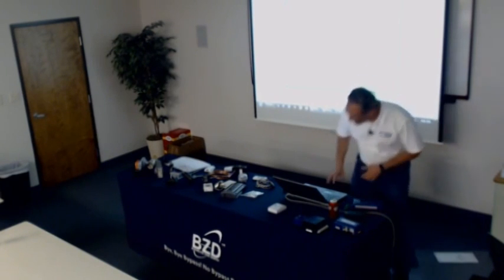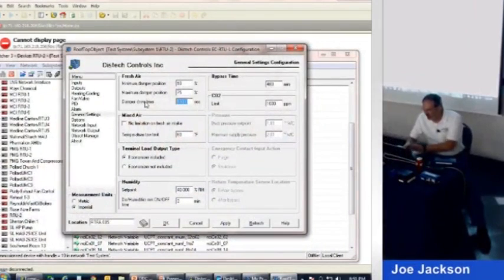So it keeps track of how long it told it to drive open, how long it told it to drive closed, and from that information it can tell where it's at. So if you were using a floating point actuator, which is really inexpensive, it would keep track of this. Let's say it was a standard 90-second actuator. You put in 90 seconds there and you're good to go.